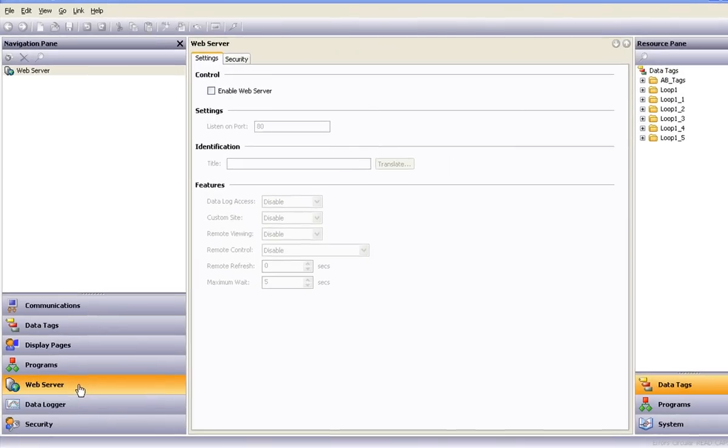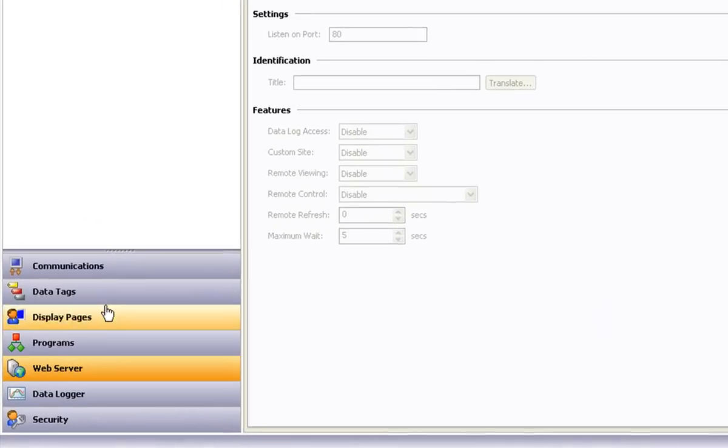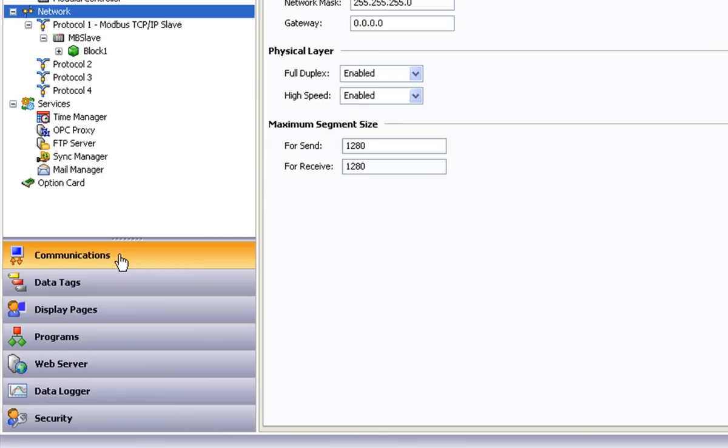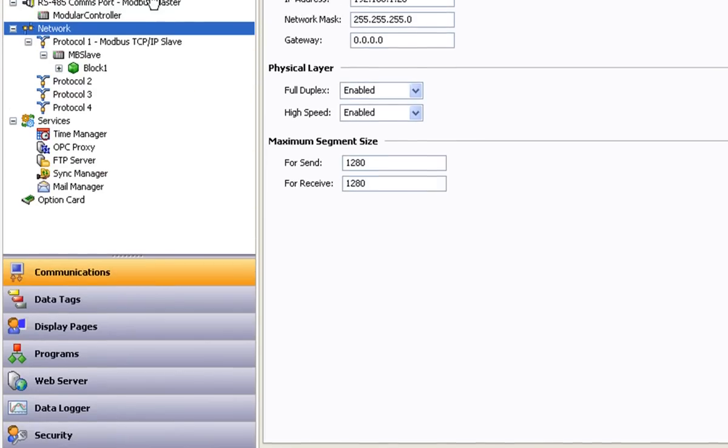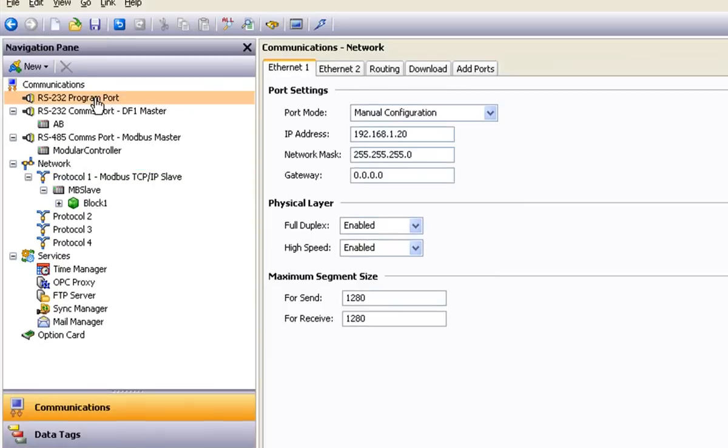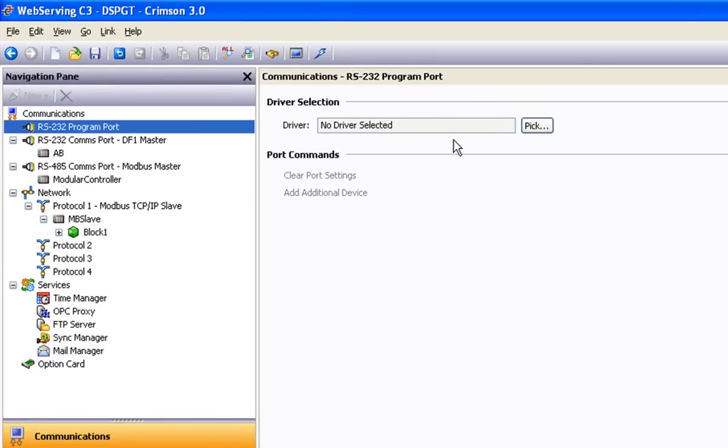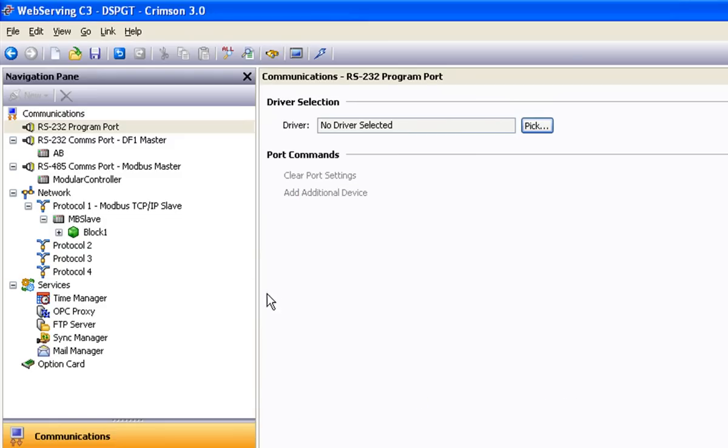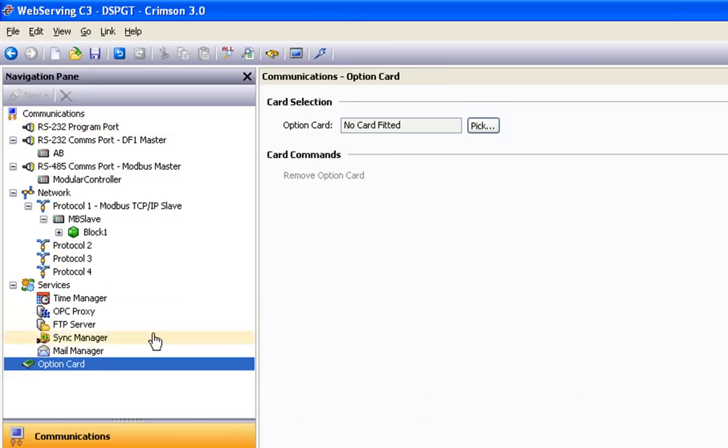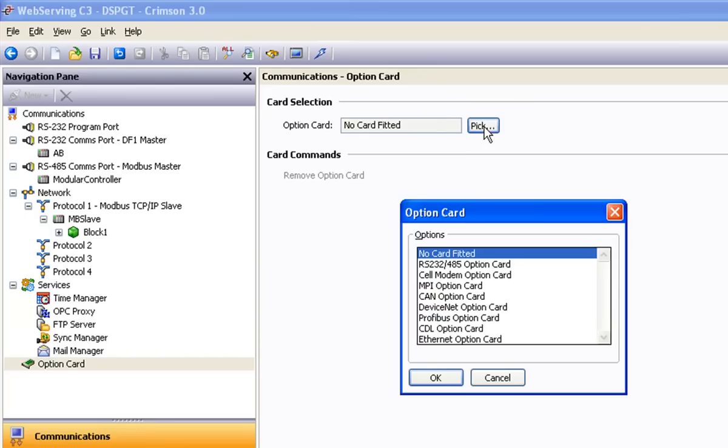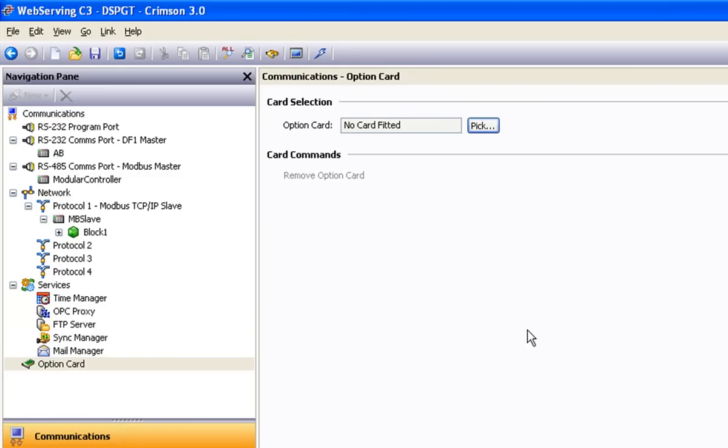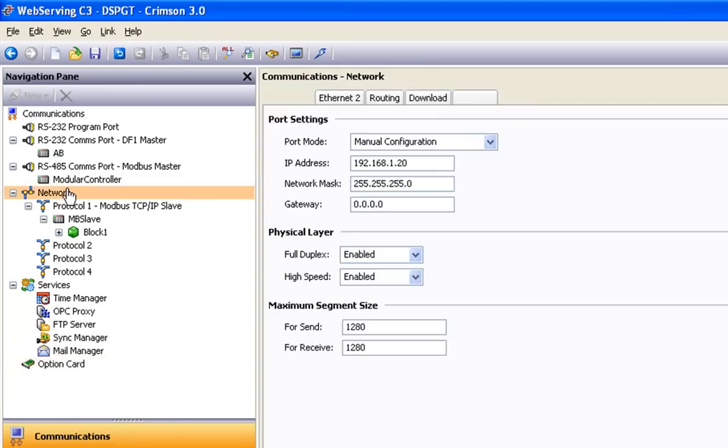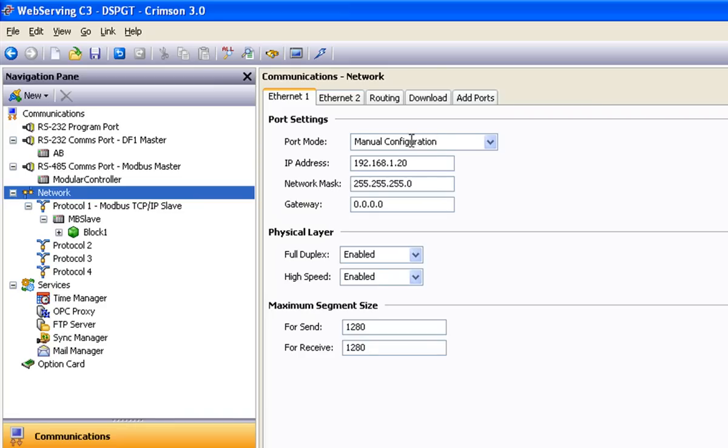The first reference we need to make is to the communications section. Be aware there's more than one way of accessing our product to make use of the web server function. For example, if the IT department doesn't want to punch a hole in the firewall to use an Ethernet connection, you can use a serial modem. Red Lion recommends using multi-tech modems. Another way to get the job done is to make use of Red Lion's cell modem option card for remote access over a cellular network where a wired broadband Ethernet connection may not be available. In this example, I'm using the Ethernet port with its mode set to manual configuration.